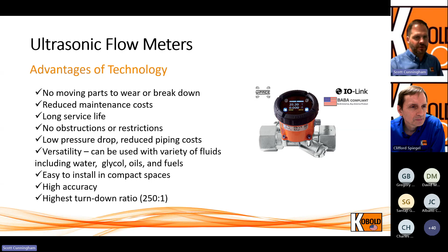They're extremely high accuracy, and they have what's referred to as a really high turn down ratio of 250 to 1. That means in terms of range, with traditional flow meters, maybe 10 to 1 is what you might get from a variable area or paddle wheel. And when you're talking 250 to 1, that means you can go from 1 GPM all the way up to 250 GPM, and that's a huge range in which you can measure. Anything else to add on that slide, Cliff? No, it's pretty basic.